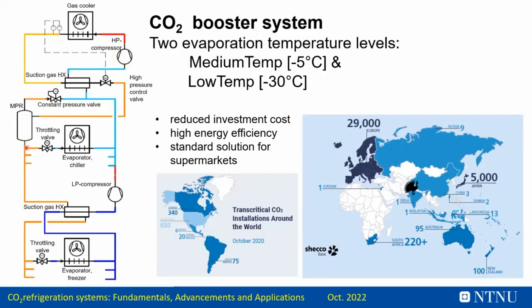The liquid goes to all the different chillers, the medium temperature mode, while other liquid goes further down and is throttled into the evaporators of all the freezing cabinets. They help to subcool and superheat. The suction line heat exchanger helps to subcool the liquid but superheats the vapor of the LP compressor, and they again are mixed, and then the loop is closed. Very efficient, very common nowadays.